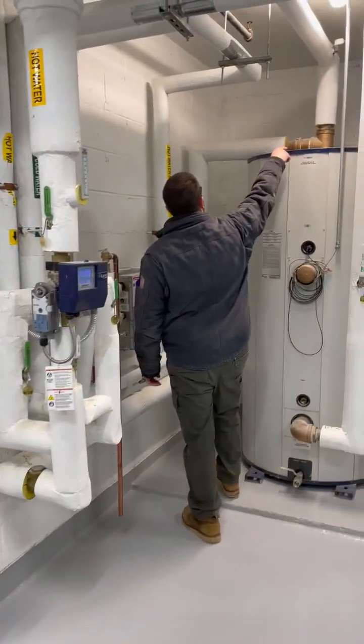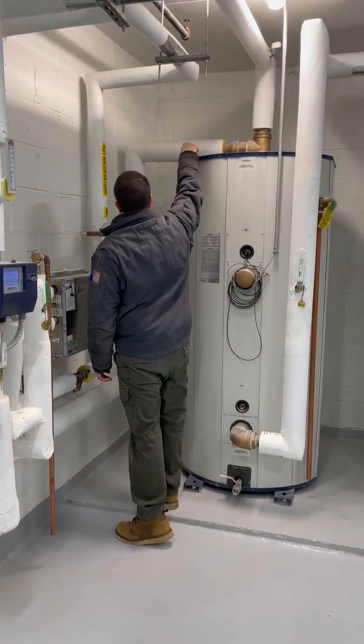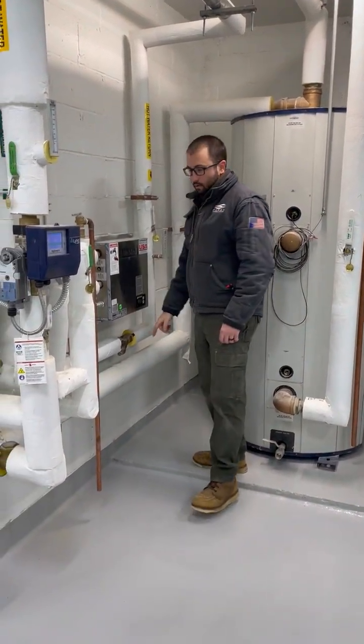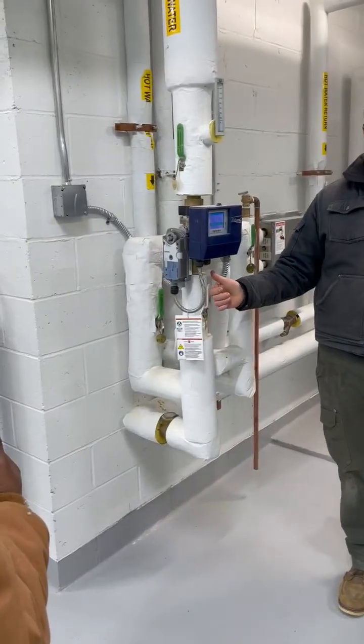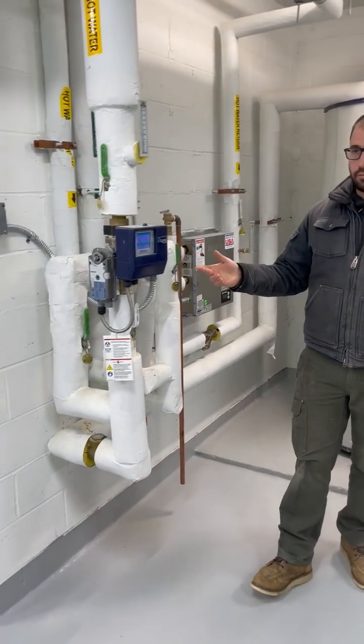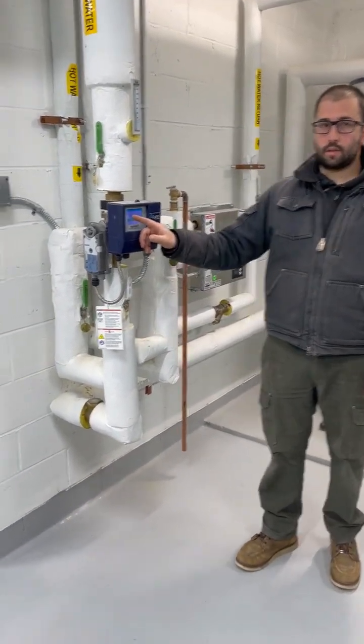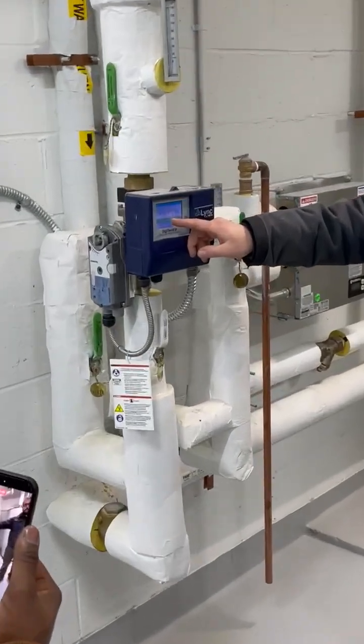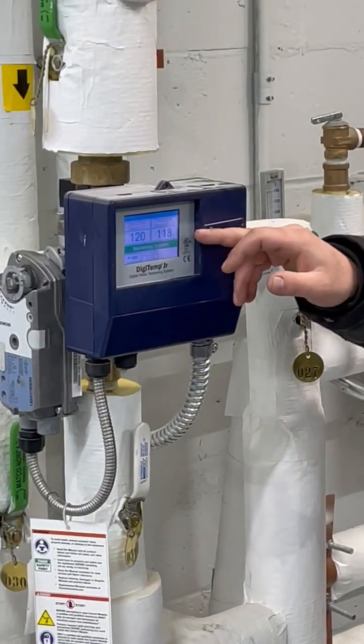So now we can just turn around again, and that's where this line comes in. This branch off the T comes down, goes through here, and goes into the hot side of our mixing valve. Now this is our digital mixing valve. Your set point is 120 degrees. We're at 118 degrees right now.